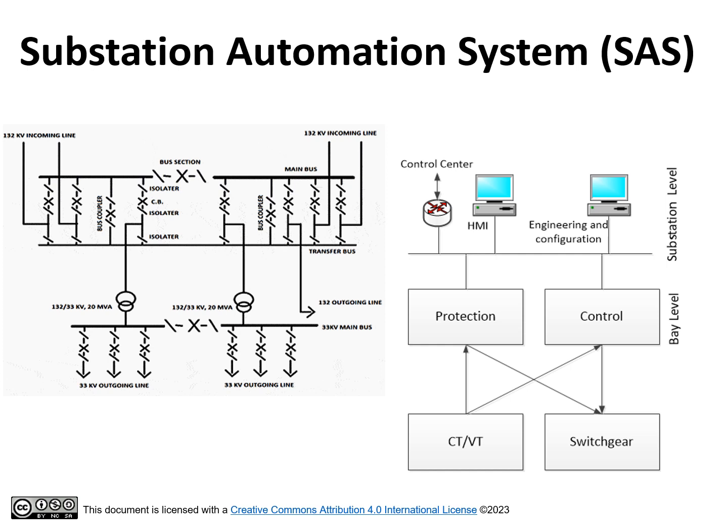Substation automation systems can be monitored and configured using human-machine interface and configuration workstations. In addition to the local human-machine interface, substations are connected to a remote control center. Old substation automation systems use analog signals and copper wires to hardwire measurement equipment and switchgear with control and protection systems. Hardwiring measurement and control signals is a tedious and costly process and hard to reconfigure.